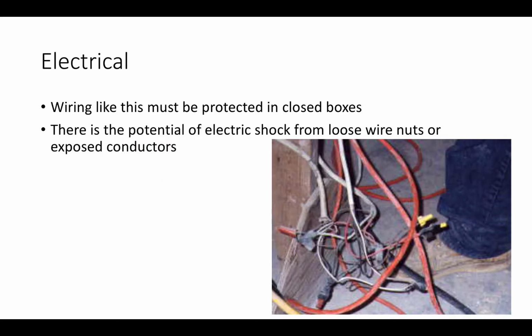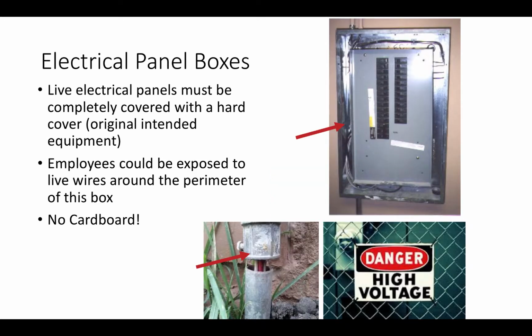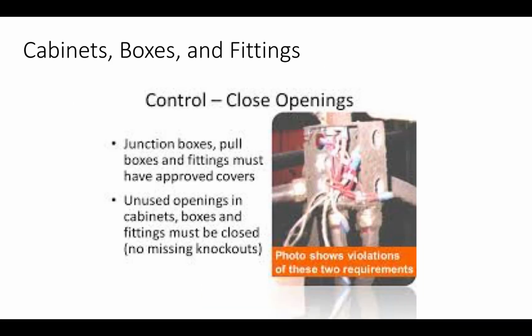Wiring must be protected in closed boxes. There's a potential of electrical shock from loose wire nuts or exposed conductors. Okay, electrical panel boxes. Live electrical panels must be completely covered with a hard cover. Employees can be exposed to live wires around the perimeter. You cannot use any cardboard as protection. Junction boxes, pull boxes, and fittings must have approved covers. Unused openings in cabinets, boxes, and fittings must be closed. You cannot have any missing knockouts.